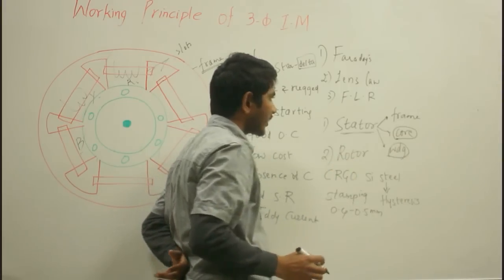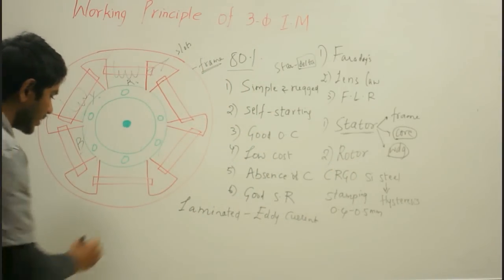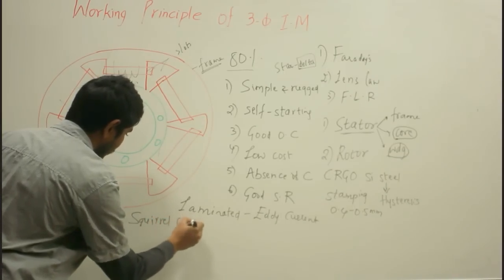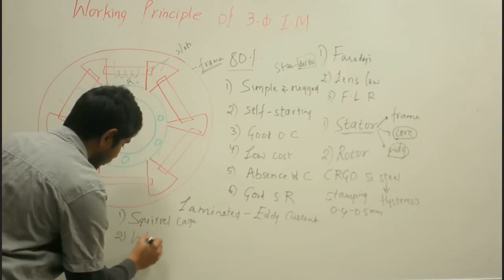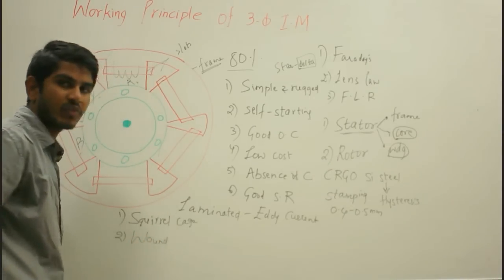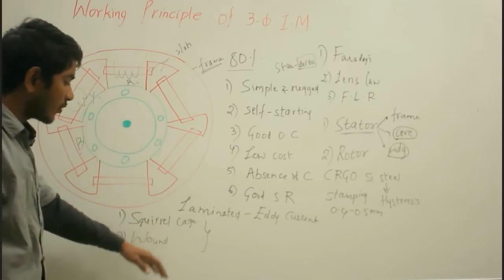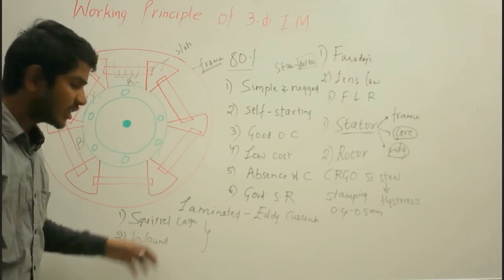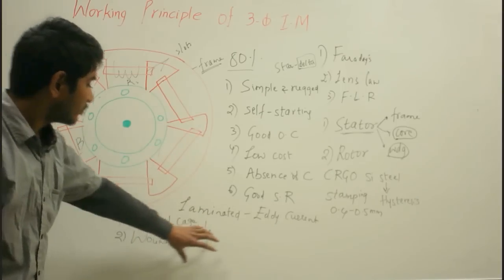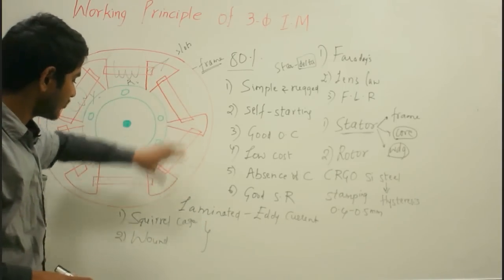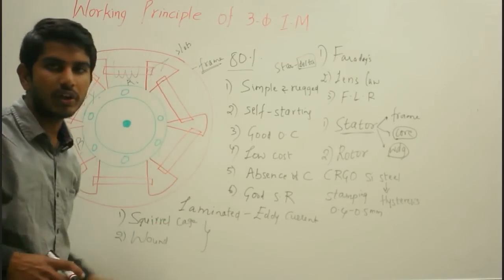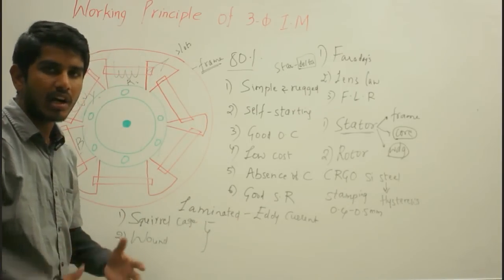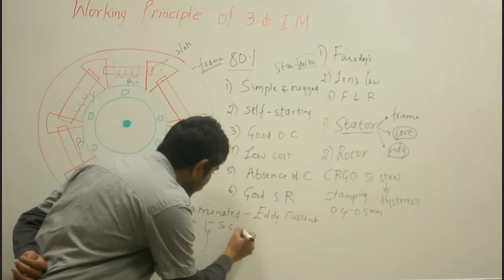Coming to the rotor, it can be classified into two types: the squirrel cage type rotor and the wound rotor or slip ring rotor. Based on the type of rotor, we have two types of induction motors: squirrel cage type and wound or slip ring type. The stator part is the same for both. In squirrel cage type, the rotor conductors can be aluminum, brass, or copper, and they are permanently short-circuited through end rings.